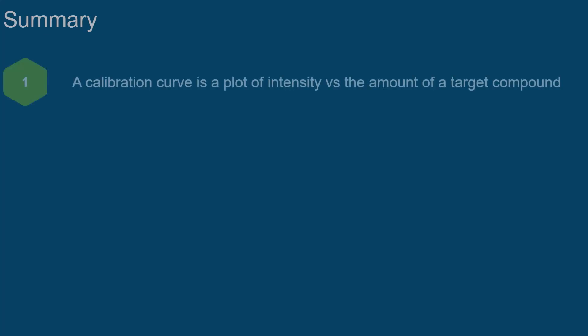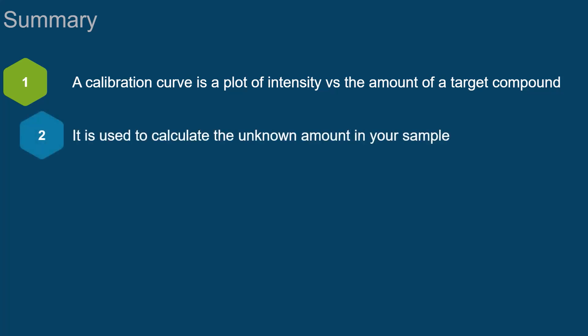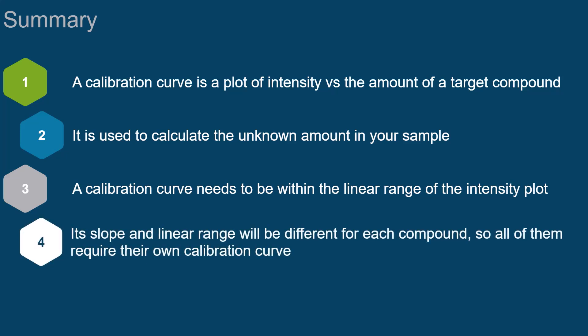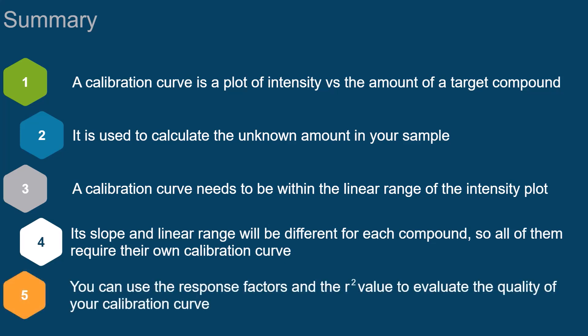In summary, a calibration curve is a plot of intensity versus the amount of a target compound, and you use it to calculate the amount in unknown samples. It needs to be within the linear range of the intensity plot. Its slope and the linear range will be different for each compound, so all of them require their own calibration curve. You can use the response factors and the R-squared value to evaluate the quality of your calibration curve.